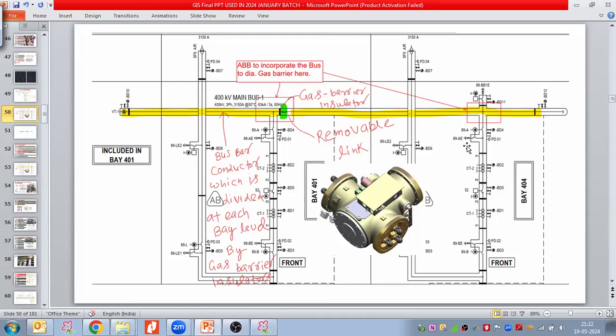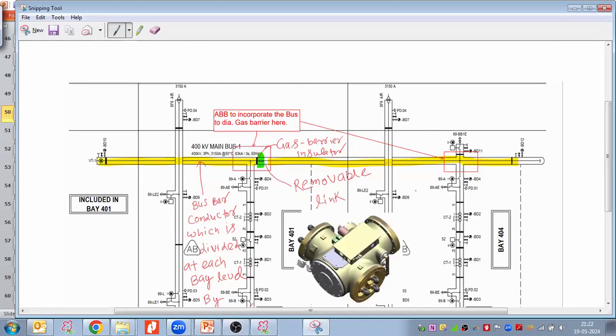See, this is a 400 kV substation with a 1.5 breaker bus bar scheme. If you see here, what is this one indicating? Bus. The common bus bar, right? Yes, sir, they are indicating the common bus bar. Let me take the snapshot. After these study discussions, I hope you are all capable of asking for the drawing and reviewing the gas SLD drawing as well, right? Isn't it?